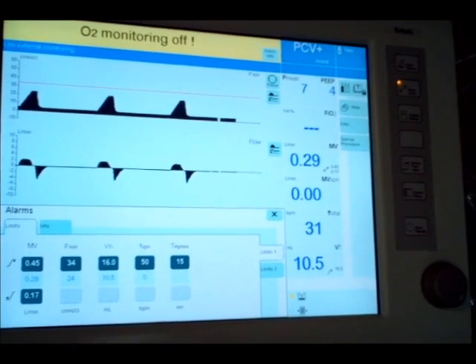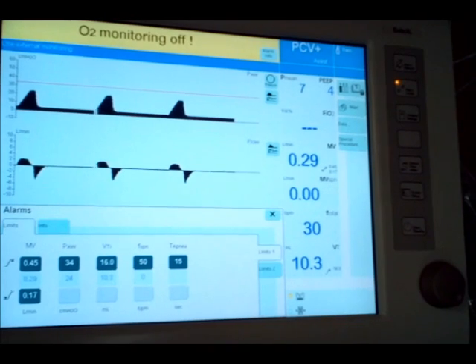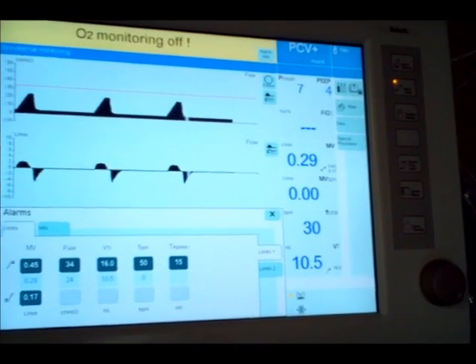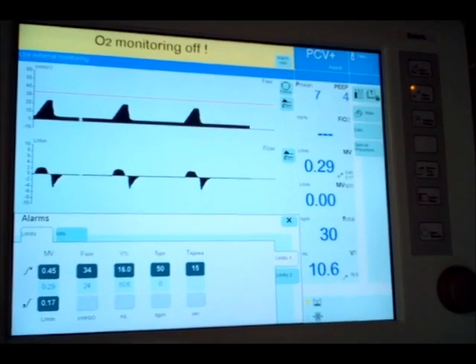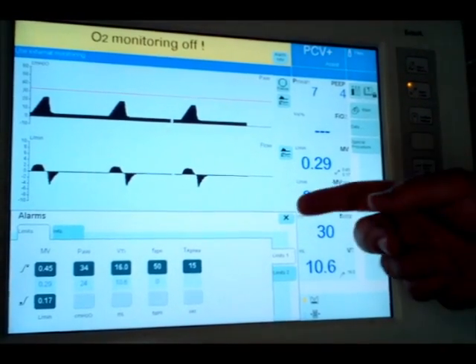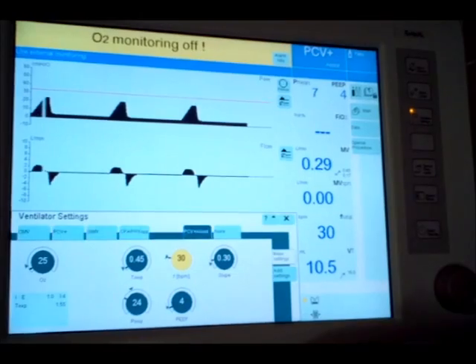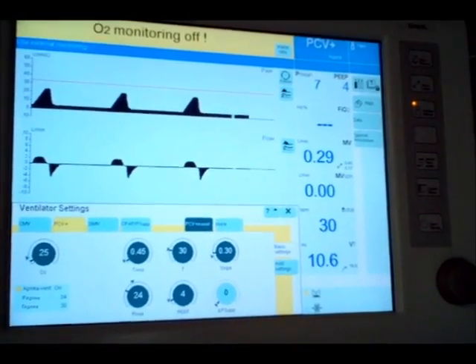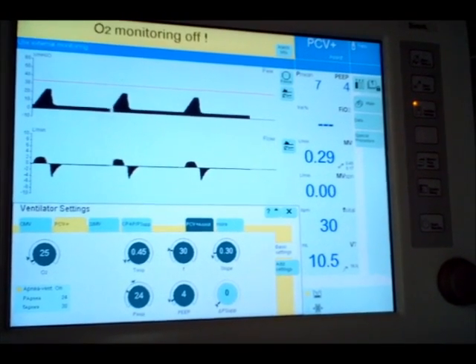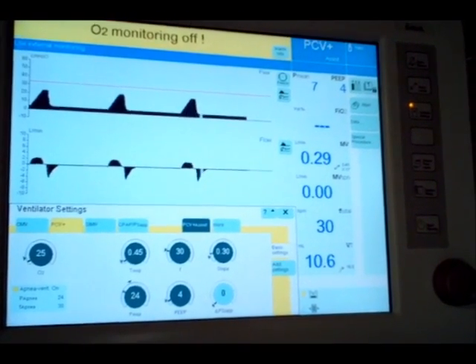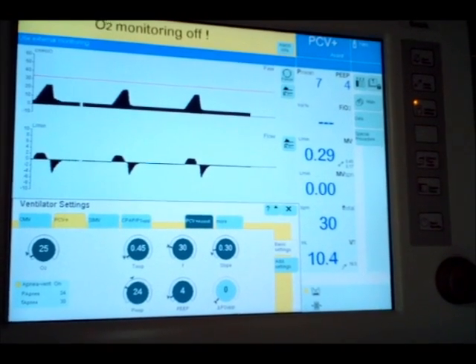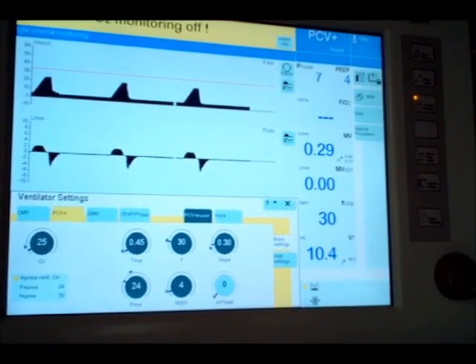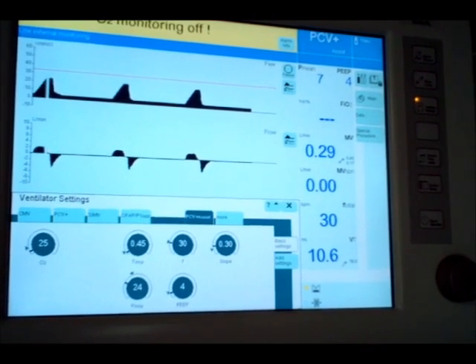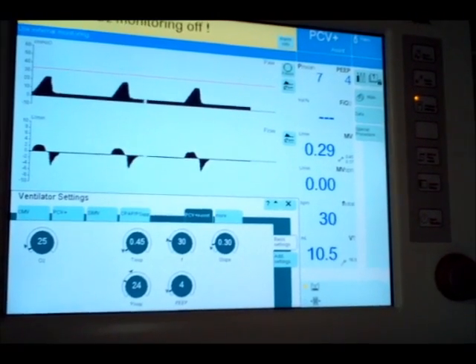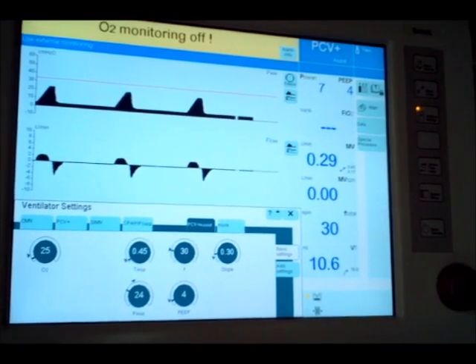And then we have, in this semester, we'll do a pressure control plus pressure support mode. Okay, so you might want to highlight or underline A there again. Now we're going to use the PCV plus, and depending on what's available in my first row there. Let's just do some new settings. Let's do 45 here. We'll do a PIP of 22. I'm going to go to 21%. Maybe an inspiratory time of 0.40. PEEP of 3. And now we'll have pressure support.